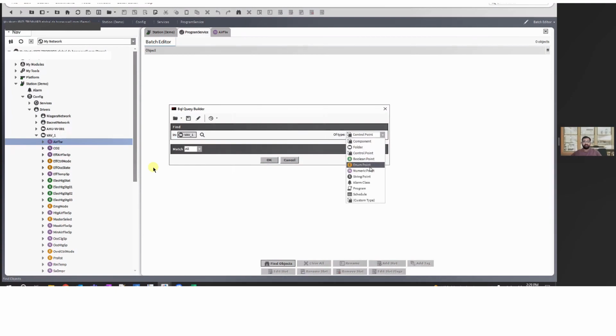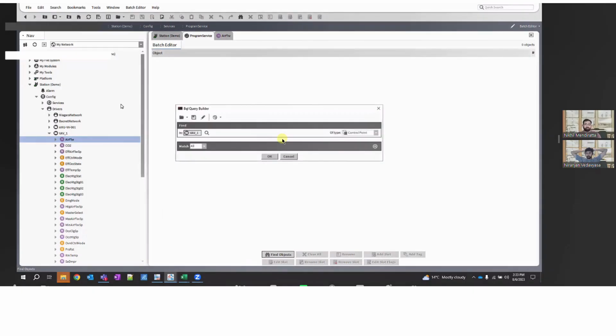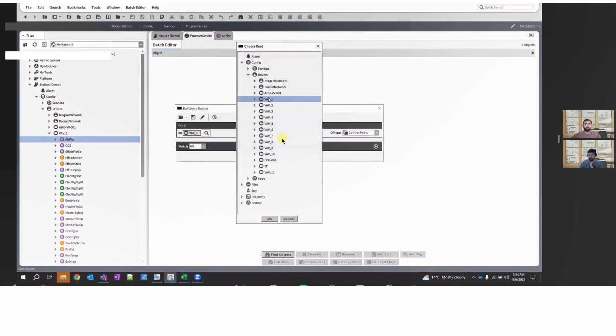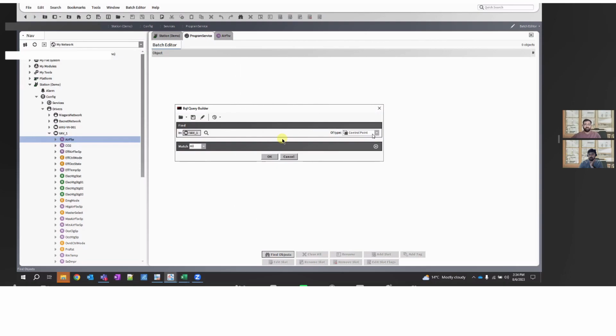Then underneath, I can define what I want. Let's narrow down to one VAV and modify units of only that VAV's typical points with units, let's say airflow. So I've narrowed the scope to VAV1. For type, I can choose control type, which will search all Boolean, enum, and numeric points. In this case, I know I don't have any Boolean or enum point with airflow, so I'll use control point.